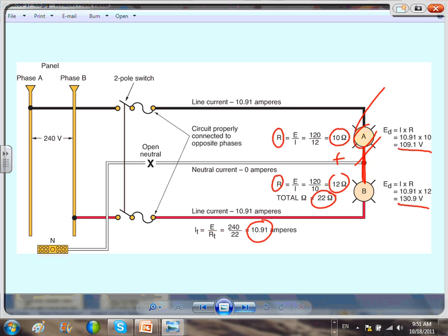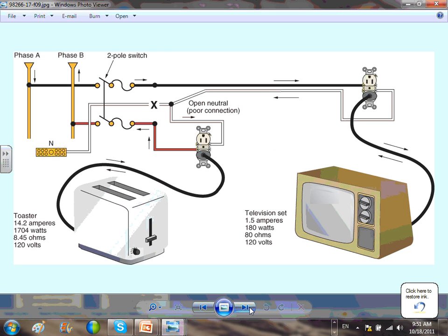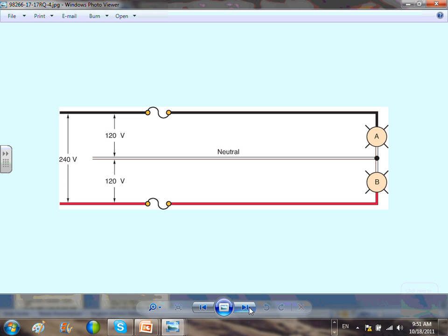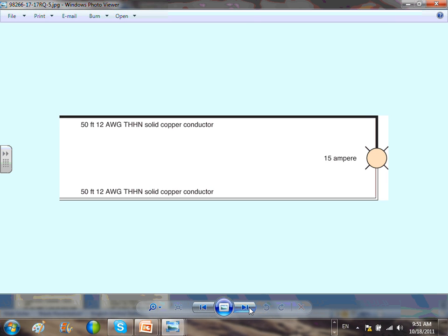Multiply it by each one of these resistors, and then you can see, after you disconnect the neutral, the distribution of voltage is going to be screwed up. Any question, guys, about this? Very, very important. What happened to your equipment when you have an open neutral? You just killed your equipment.